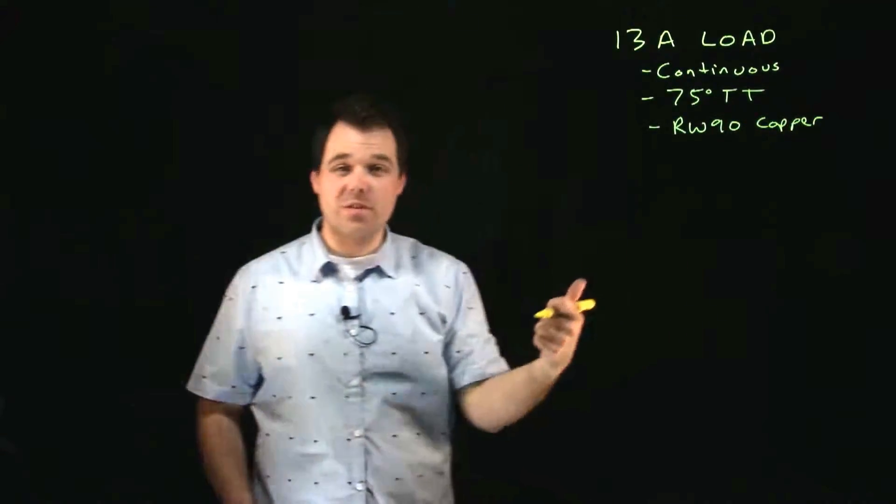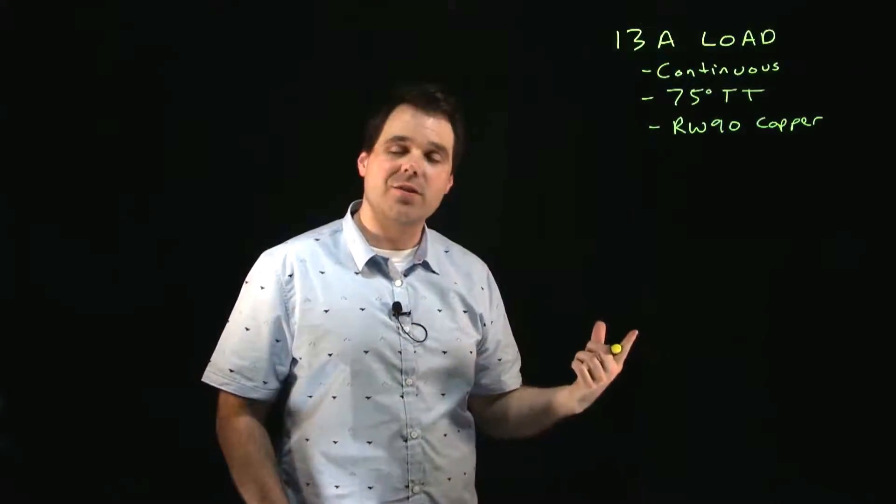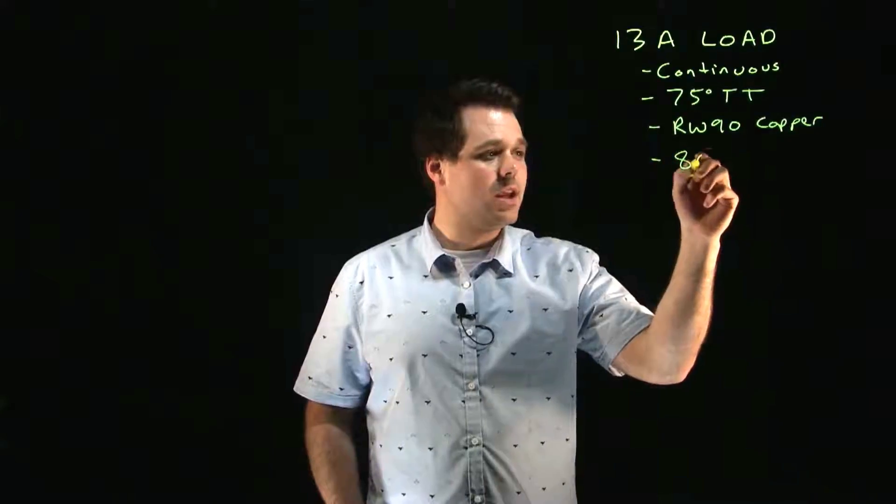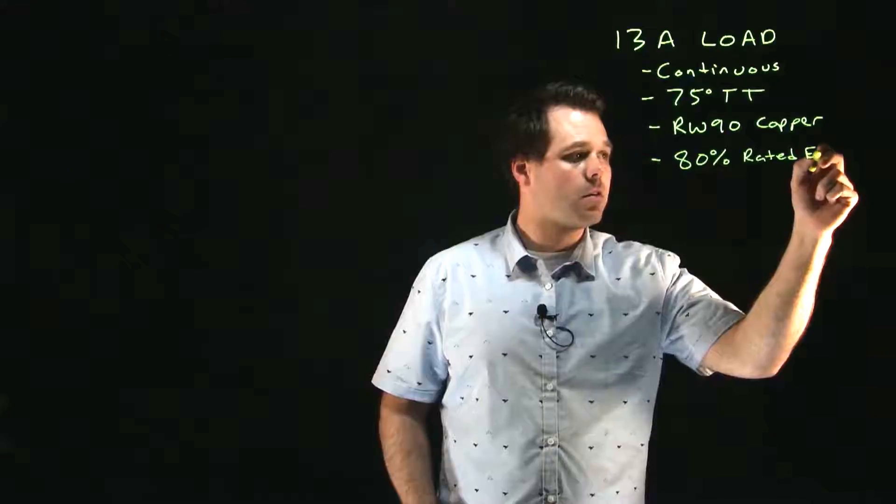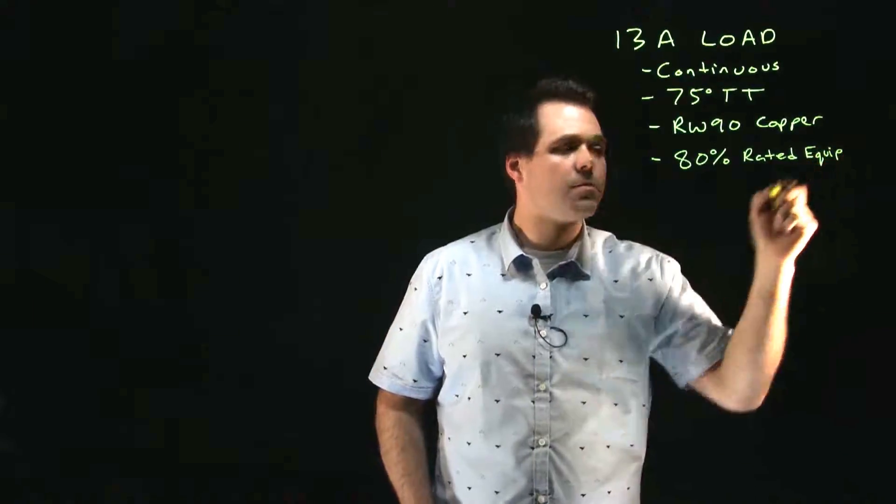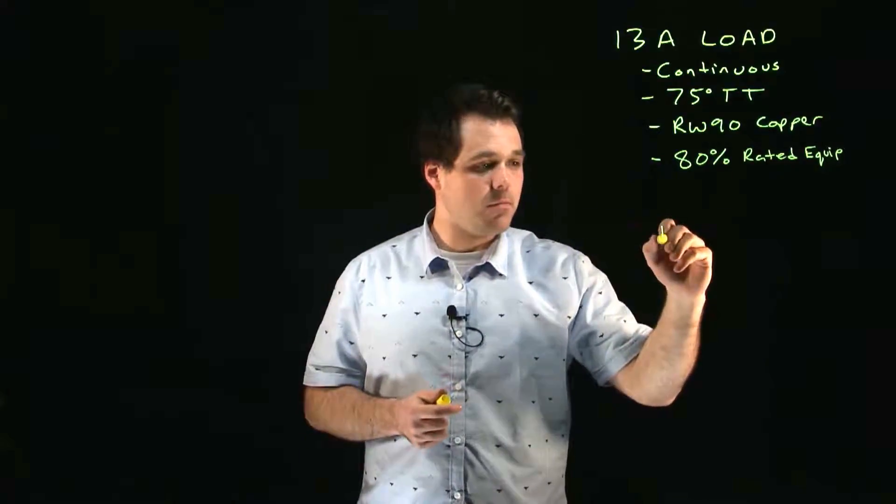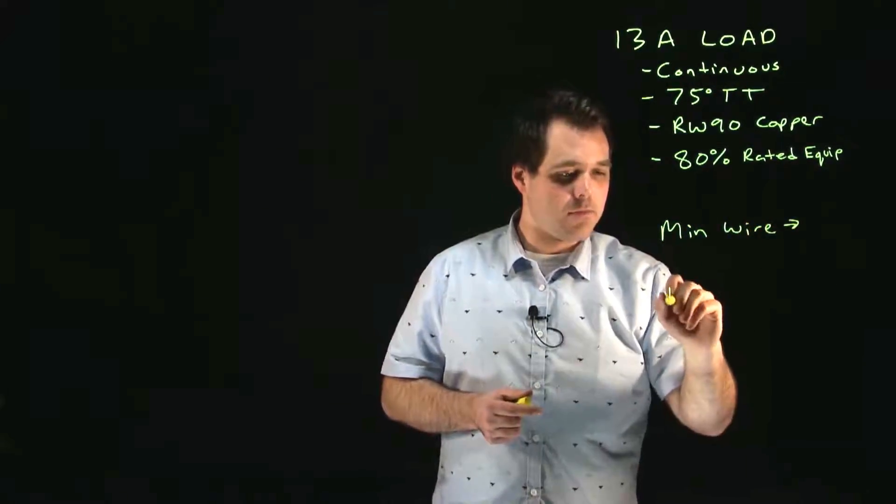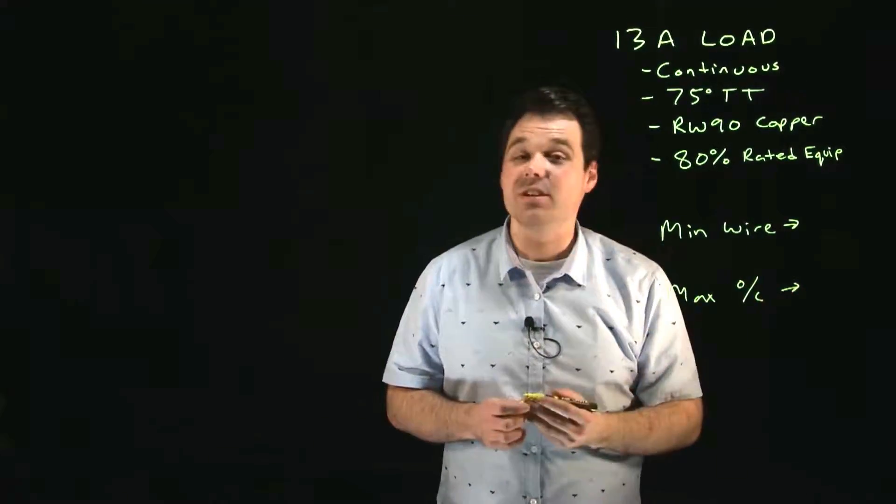I'm going to say not more than three conductors in a conduit, not over 30 degree ambient temperature, and I'm also going to say that it is connected to 80 percent rated equipment. So with this information I intend to size the minimum wire and the maximum OC that would be permitted for this installation.